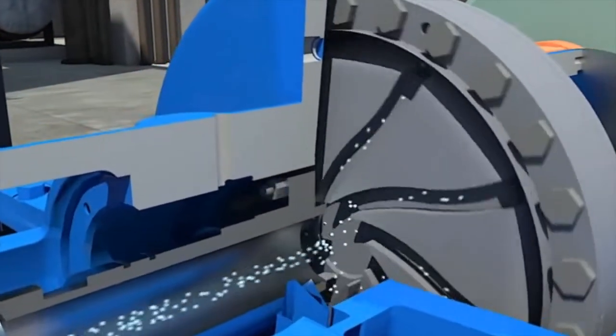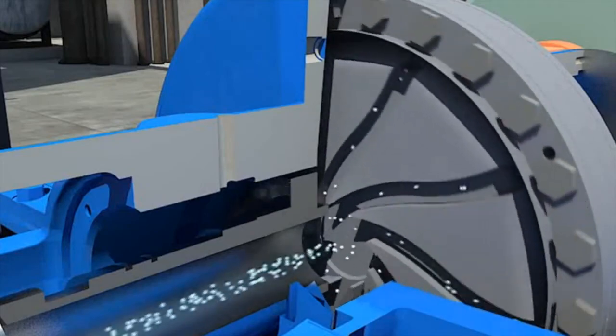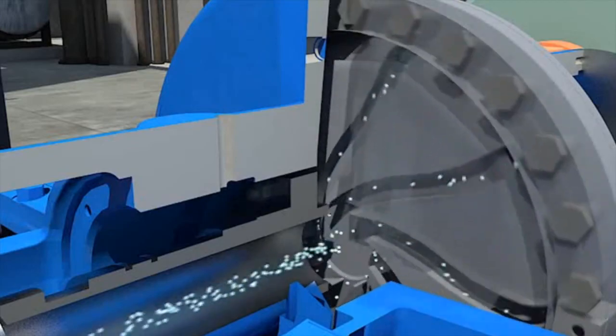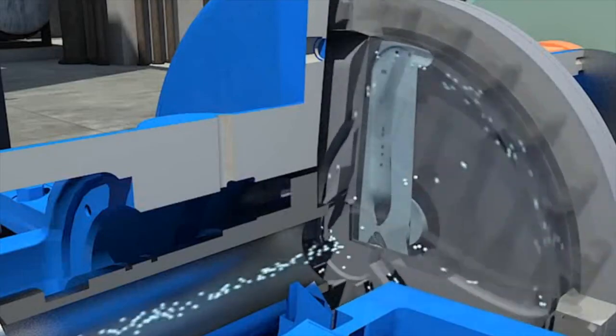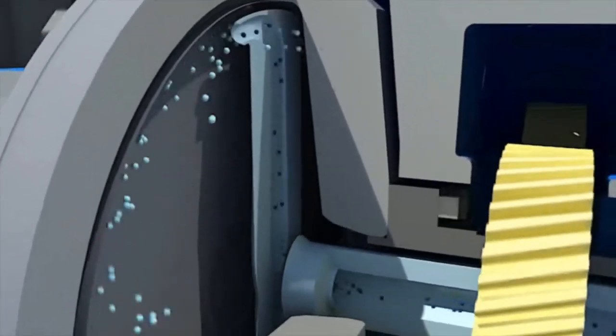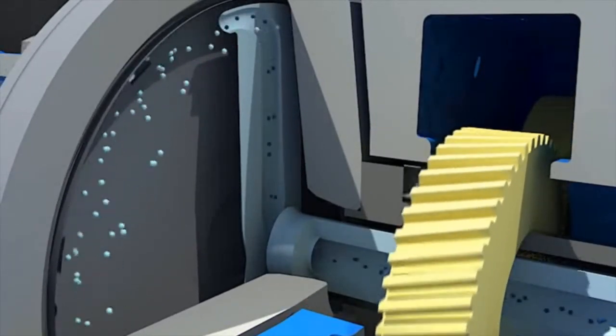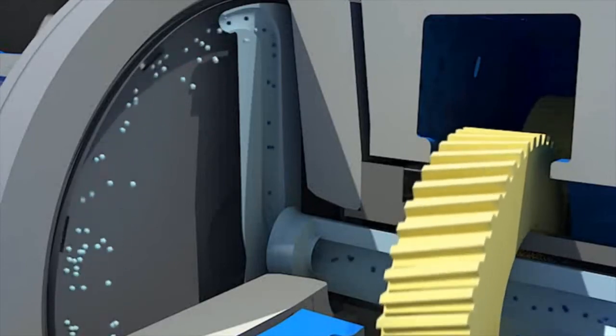The fluid enters through the shaft on one side, passes through the vane channels in the rotor assembly, and is introduced through the holes into the rotor cavity, where it spins along with the rotor, and the fluid is then forced into the pitot tube. And here, unlike the overhung, the fluid is going in the opposite direction, and the discharge shaft works also to support the bearing. Everything is all arranged in a very compact manner.